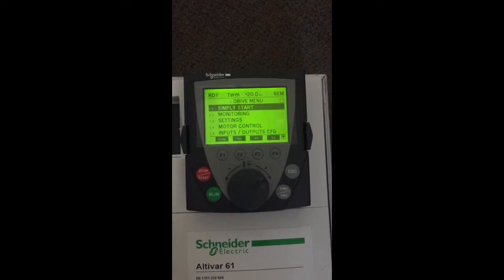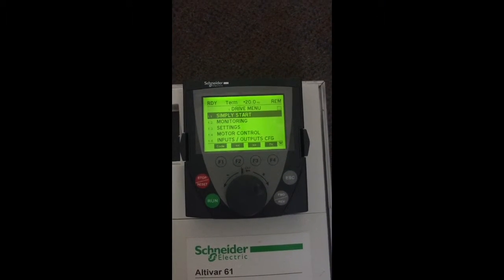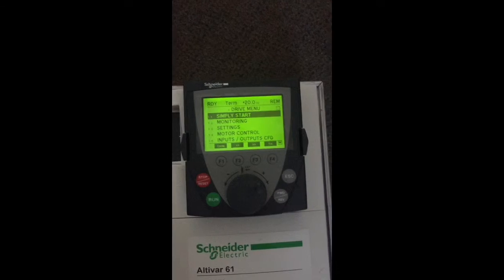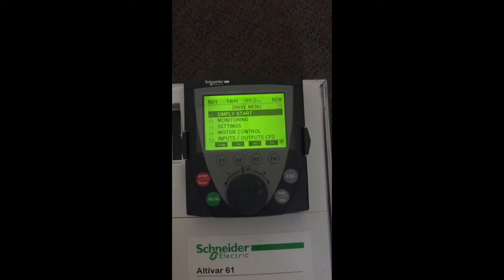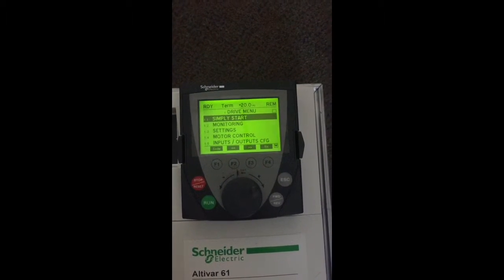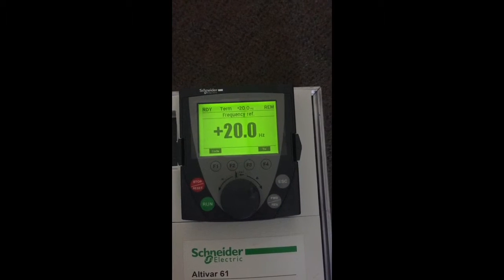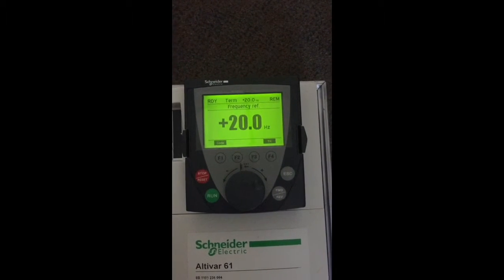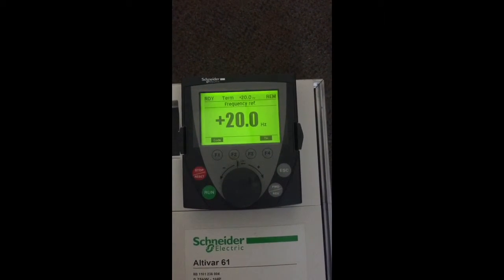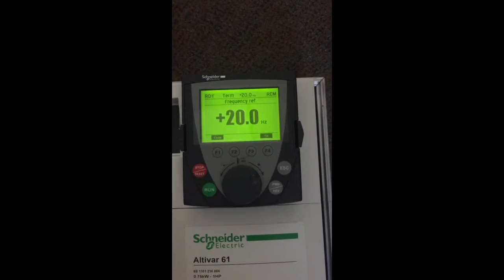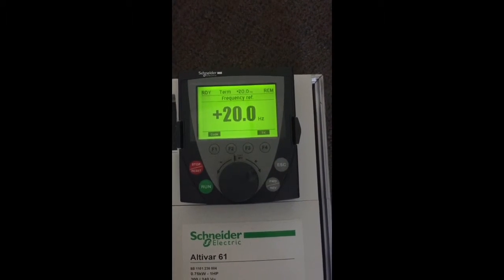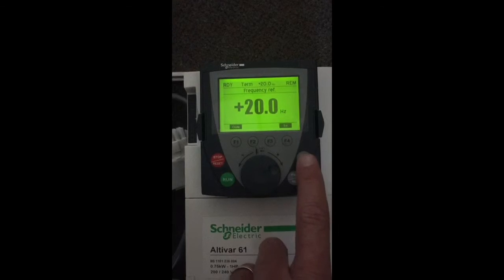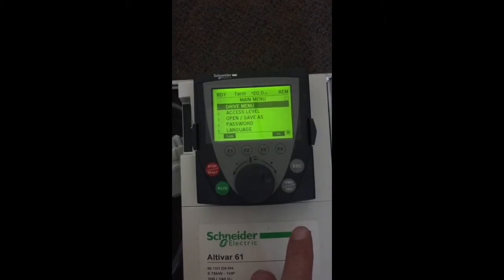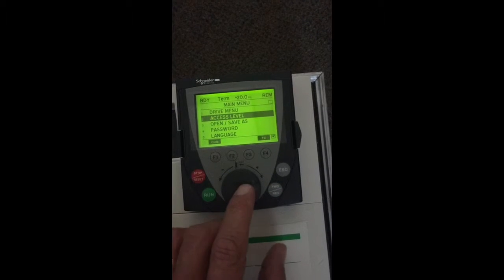I'm going to cover the basic setup of the Altivar 61 drive for your motor parameters and input through a 4 to 20 or 0 to 10 volt input, either from a temperature sensor or pressure transducer. First screen you saw is the drive menu. You will enter into the access level.